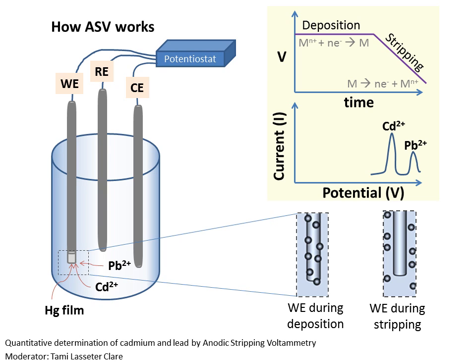The potential change can quantitatively tell you how much of each type of metal there was in your sample. This is a three-electrode measurement system, where there is a working electrode, reference electrode, and counter electrode, connected to a potentiostat that controls the potential or voltage applied to the working electrode. The working and reference electrodes are used to define a potential in the cell, and the goal is to keep the well-defined potential on the working electrode versus the reference electrode, and only allow the current to flow to the counter electrode.